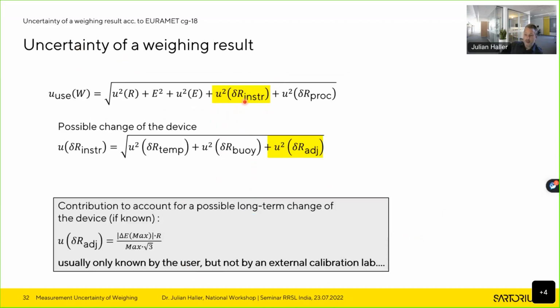One thing that is mentioned in the CG18 is a possible change of the device. Possible long-term changes of the device. And there we have a problem, at least from our perspective as a calibration lab. This is usually only known by the user, but not by us. So we just cannot take this into account because we do not have that information. But if it would be available, of course, this would have to be taken into account as well.